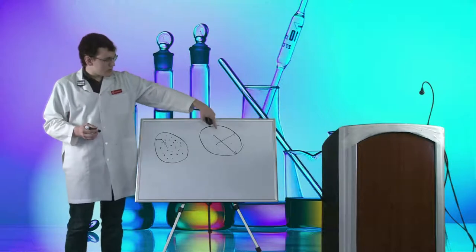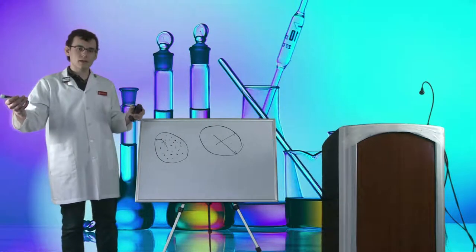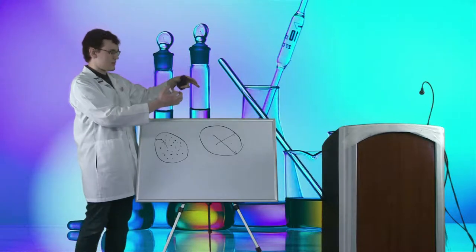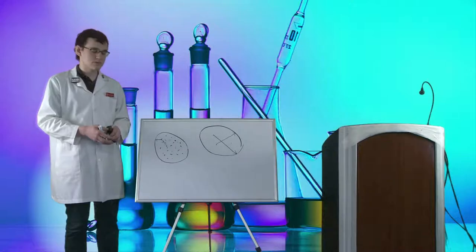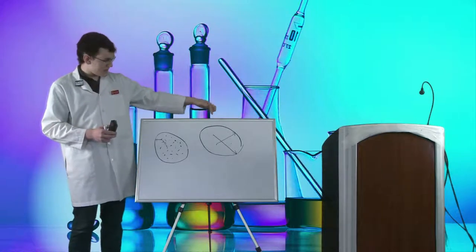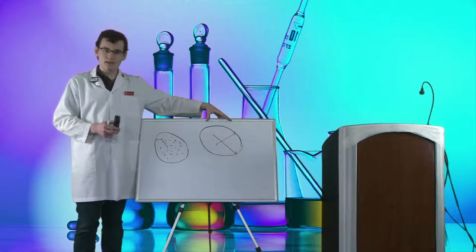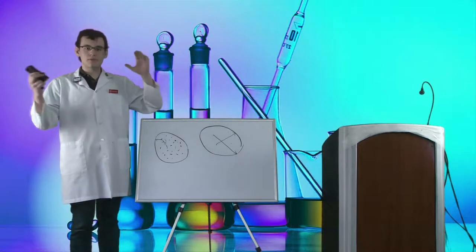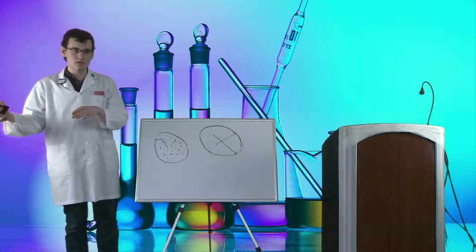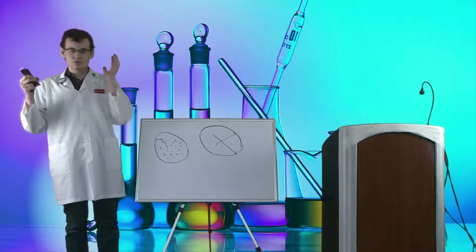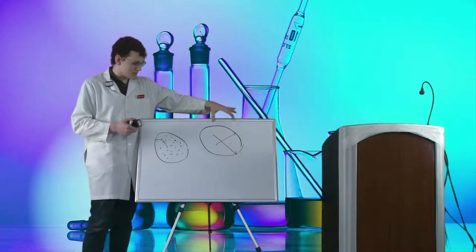We can't model this type of vacuum as a fluid like we can normal air. It's a molecular environment, and we model it as a bunch of individual particles. The fact that we have to transition from fluid flow to molecular flow is the basis of how all the vacuum pumps work, how all the conflat seals work, and why we have to have things so tightly sealed with so little dust. It's all because of this molecular flow.